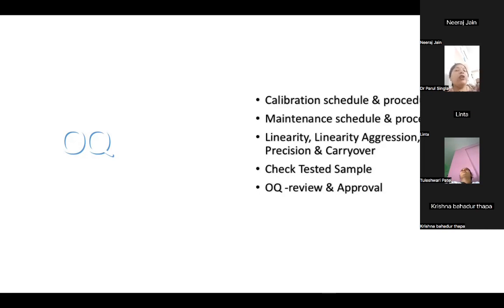Then carryover. Few equipments have disposable tips, so no carryover study is required. But for smaller equipments, where there is a single sample probe and a single reagent probe, carryover studies should be done. You have to take two samples, one low and one high, which have been reported. Run the high sample three times in duplicate, then run the low sample in duplicate three times, and see whether any carryover is there or not.